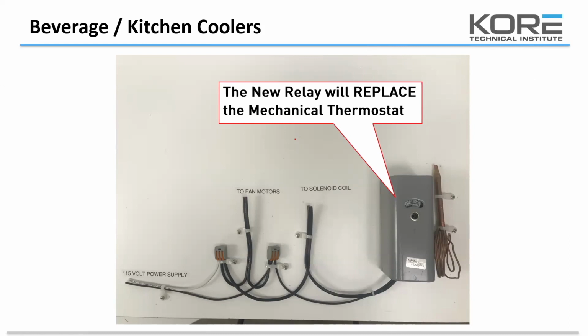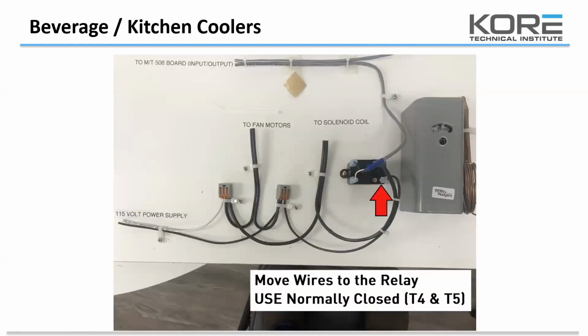So, okay, the T-stat is usually mounted up on the side of the evap coil. You'll see that the 2 wires are coming in. They are distributed out to the fan motor and the coil. All we do in this particular cutover is we simply add a relay. We bring our wire in from the control panel 508 board with our 24-volt control, attach it to 1 and 3 on the coil, and then we simply just remove the 2 wires from the thermostat.